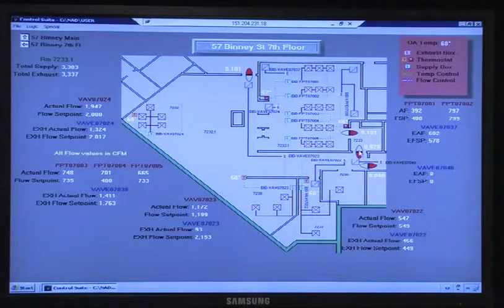So that's why these two devices, because this area out here and this area in here are the two things the pharmaceutical industry looks at for pressure relationships to anything else. These two areas here just exit out of the area of the pharmacy that we want to look at. So the most critical things that we want to be maintaining are this and this. These are going to be changed to TSI indicators. These are just Setras above the door, as I'm being told, and the values from these Setras are right here. We have to maintain certain pressure relationships between all these devices.